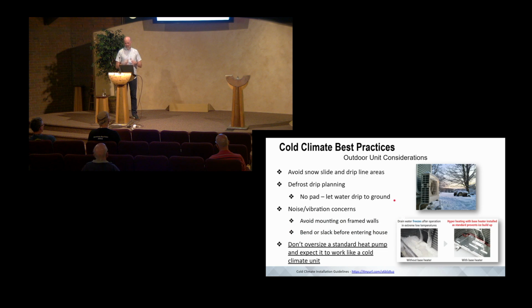Defrost water drips out of the outdoor units in the winter, that's just how heat pumps work. As it drips out, it refreezes, so potentially you could have an ice rink on a walkway. You don't want that, so stay away from walkways. A lot of people put down pads, concrete pads or faux concrete pads. I personally like pavers, and I like to see stands that lift the unit up out of the snow, with enough space for any ice or buildup, with the feet on pavers tamped down into place, so when the water drips down it goes to the ground and just goes away. The water doesn't stay there long term.